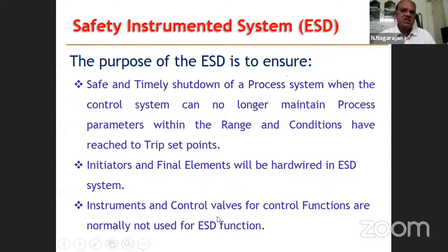Then we come into the ESD, okay, emergency shutdown system. This is an important second layer. I already told this has nothing to do with the process control layer. This is the second layer, protection layer for the process, which is called the emergency shutdown system. The purpose of the emergency shutdown is to ensure that the process is run in a safe manner with all provisions.